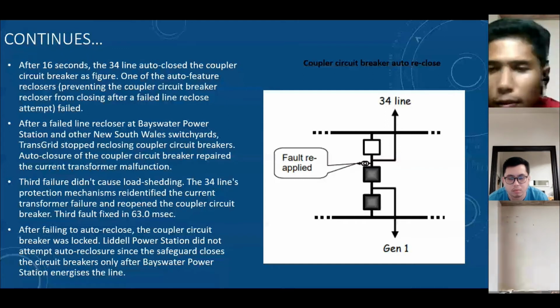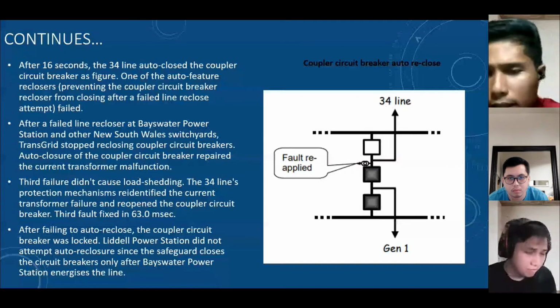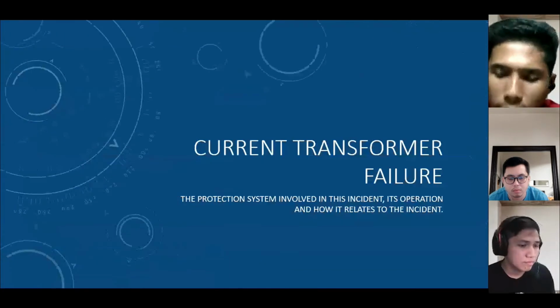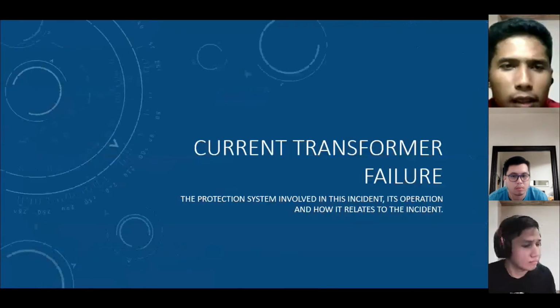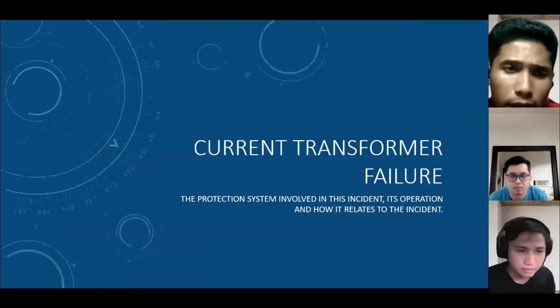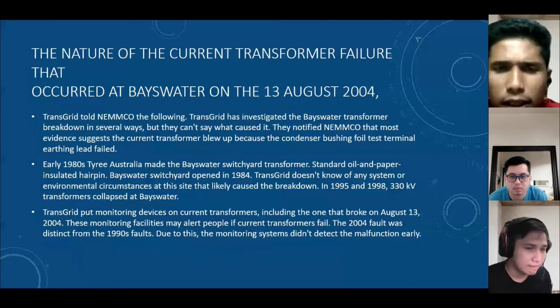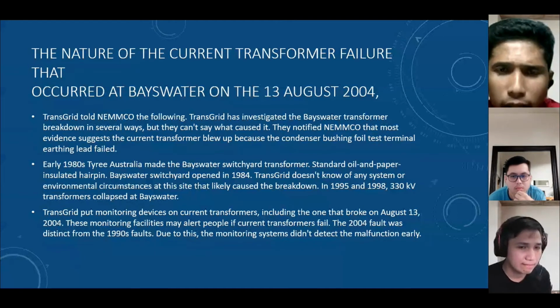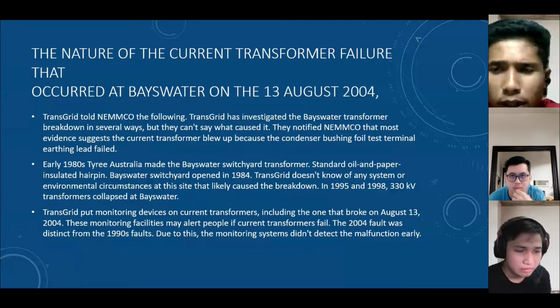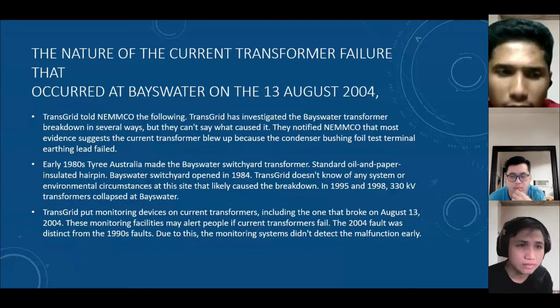Okay, how the protection systems involved in this incident operated and how they relate to the incident. Alright, regarding the nature of the current transformer failure that occurred at Bayswater, TransGrid told NEMMCO the following. TransGrid has investigated the Bayswater transformer failure in several ways, but cannot say what caused it. They notified NEMMCO that most evidence suggests the current transformer blew up because the condenser bushing foil test terminal earthing lead failed.